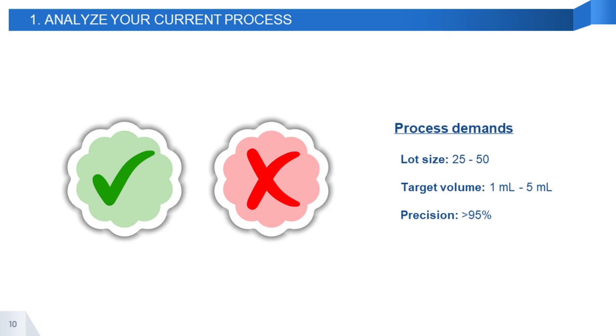Starting with the lot size, as I said before, lots were very small in our factory in its beginnings, between 25 and 50 containers. Then the target volume was from 1 to 5 milliliter, and the precision needed was above 95%. The speed is also an important demand, but with tiny lot sizes, it comes to a second place, as it does not affect too much.